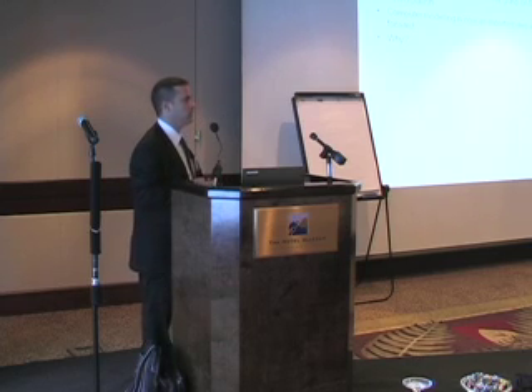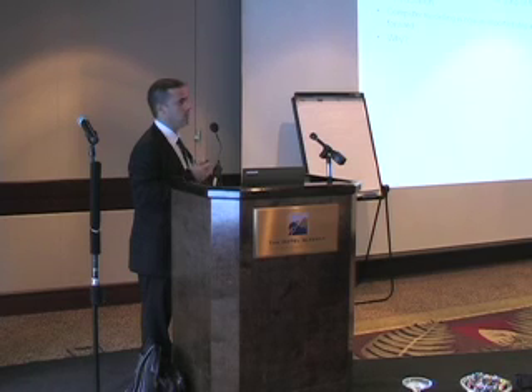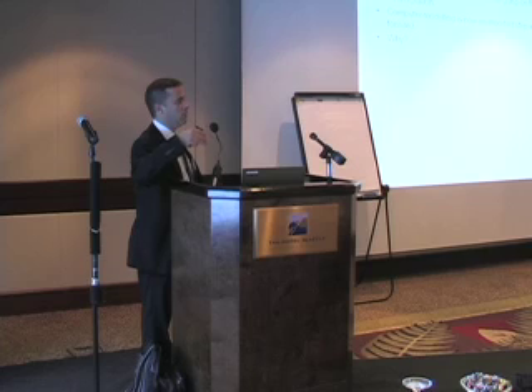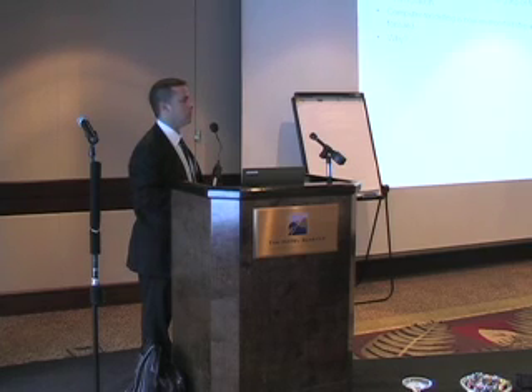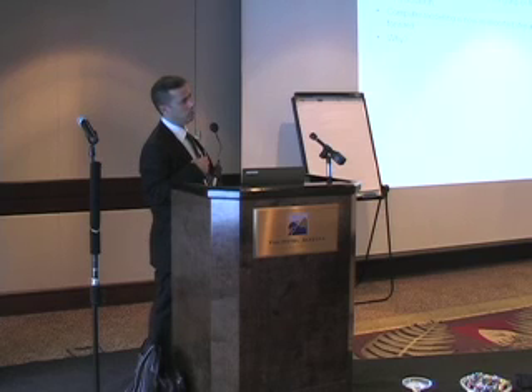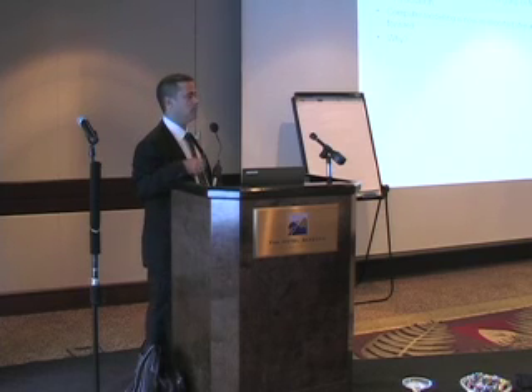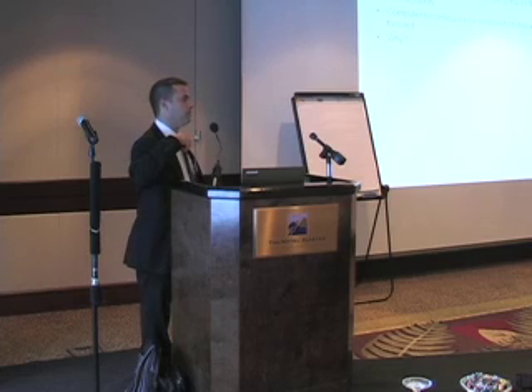You may not be able to feed enough fault current to trip the protection or trip the breaker or blow the fuse, whatever it is. So it's a challenging one that we've struck a few times, and we've had to model that in advance of going to the site and actually implementing what we're trying to do with the upgrade. It's a real one to look out for, because the last thing you want to do is build something that could potentially allow the power to stay on in some form or fashion, even though there's a fault on the line, like that example I gave.